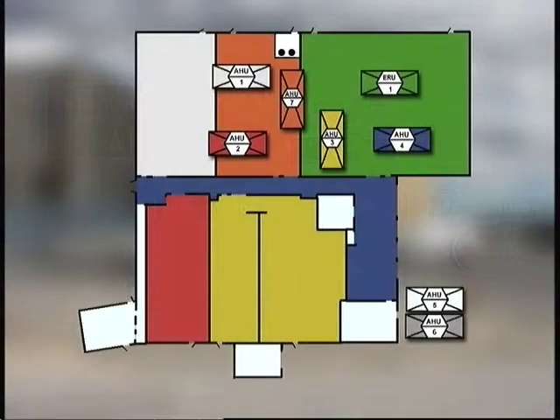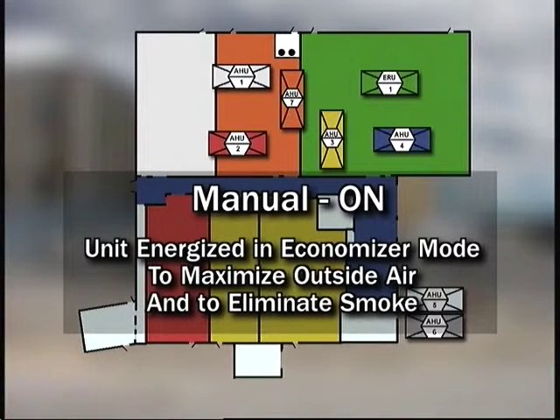Manual on, the unit is energized in economizer mode, regardless of outside air temperature, with both supply and return fans energized. The unit supplies 100% outside air to the spaces served and exhausts 100% of the air returned to the unit. This mode maximizes the introduction of outside air into the space and the removal of smoke or airborne particulates.